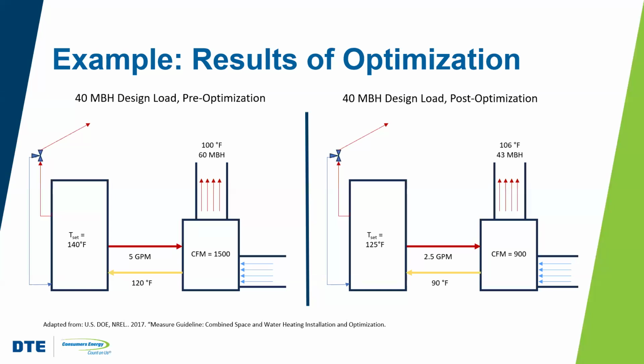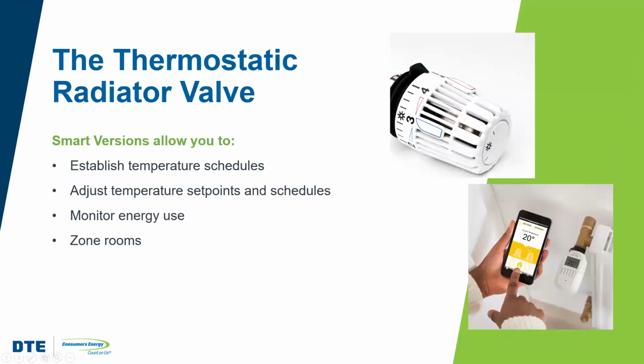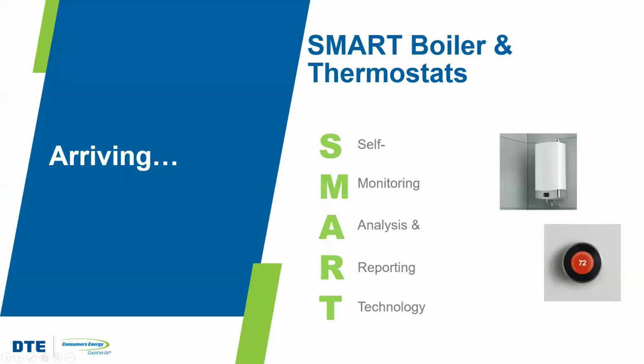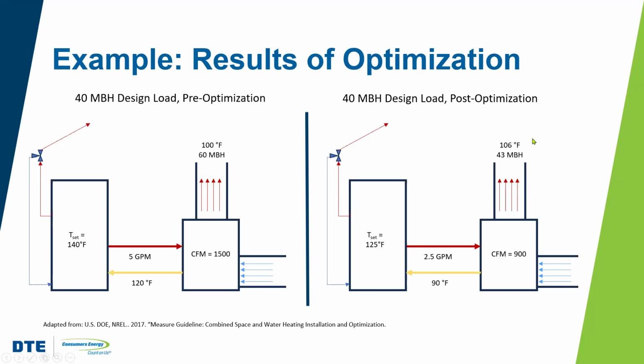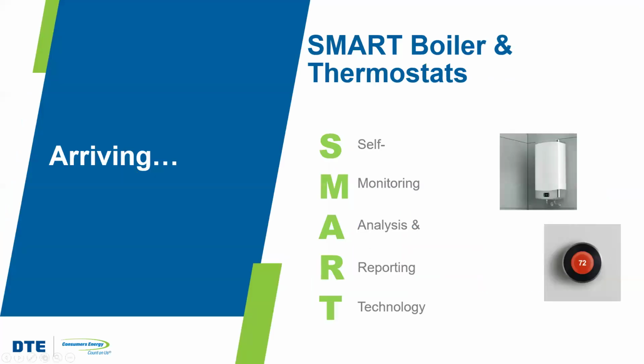We were able to lower the set point. We were able to reduce the airflow and still provide a supply air temperature that's acceptable for comfort in the system. And we can see here now that the output matches the demand a little bit better. Let me go back a little bit, right? The output actually matches the demand. So instead of the system being oversized, now it's actually matching the demand. So our costs are going to be less.